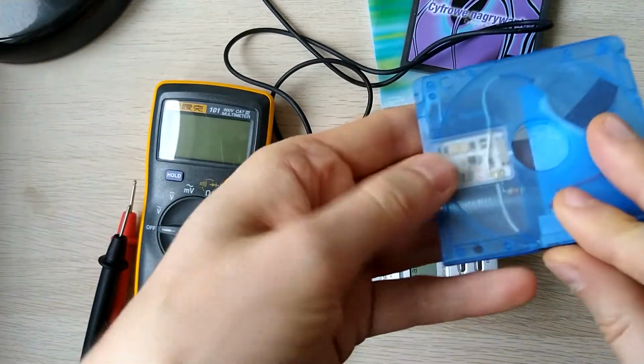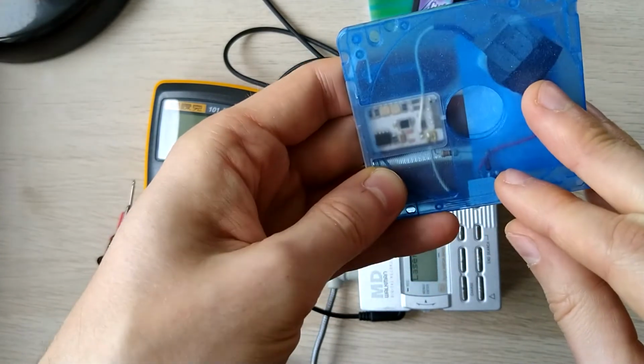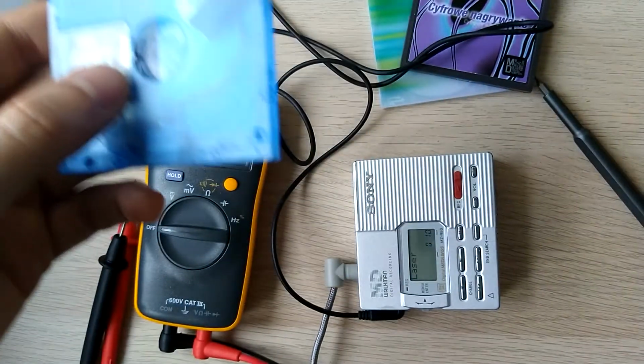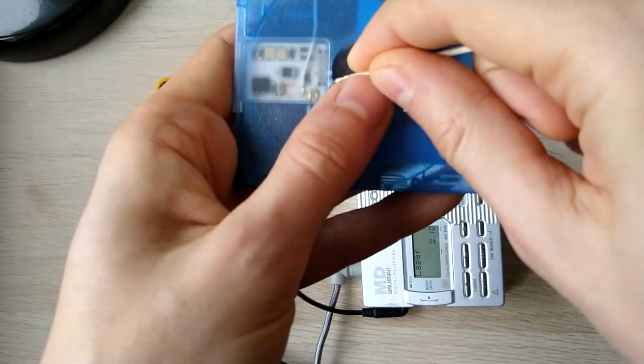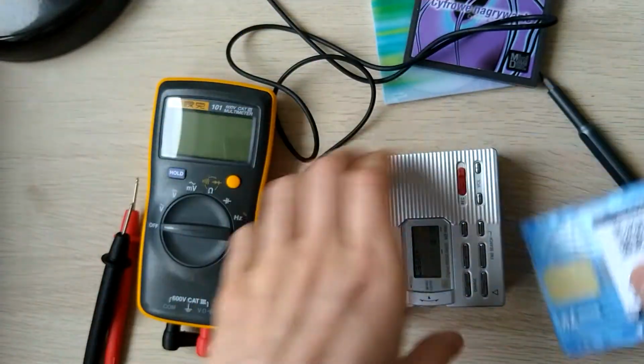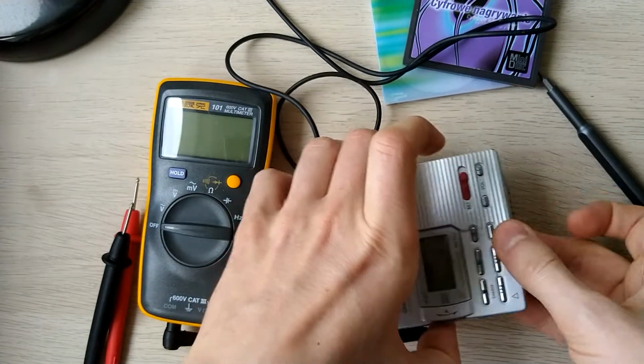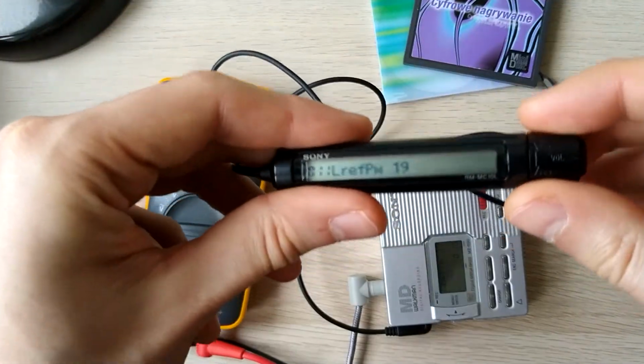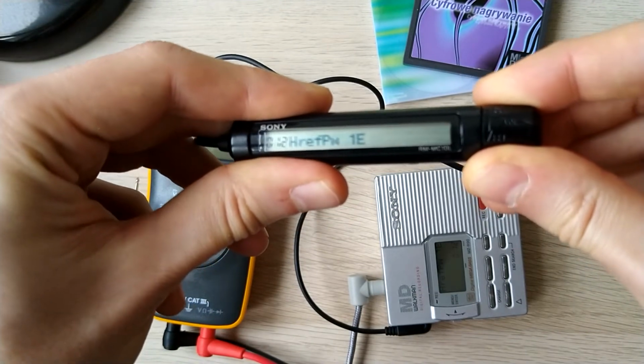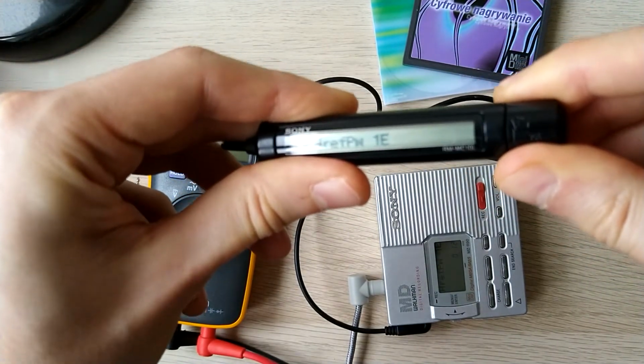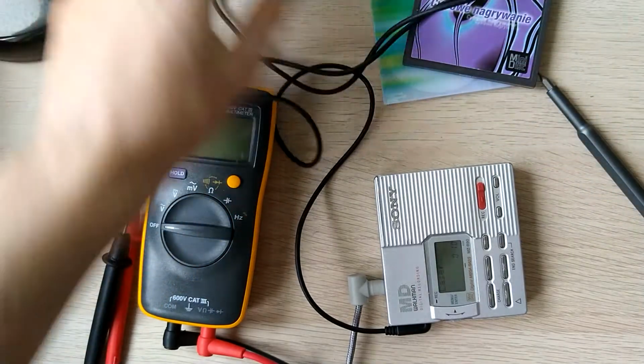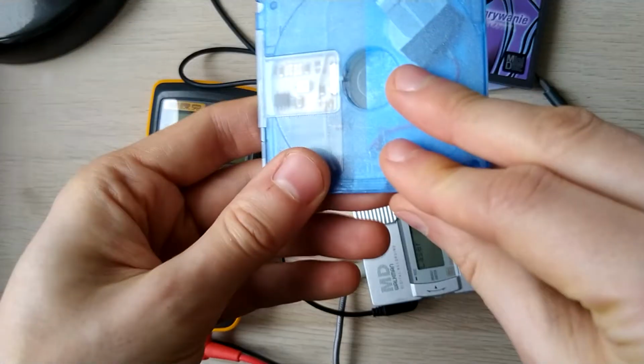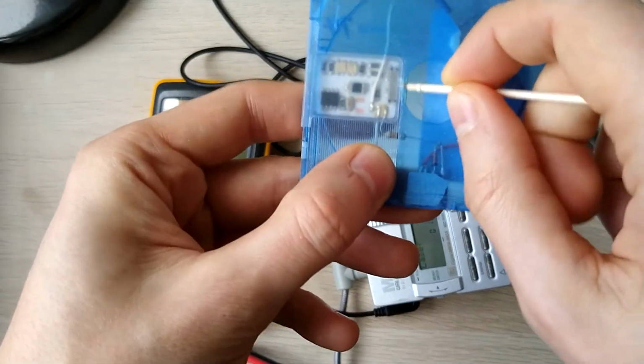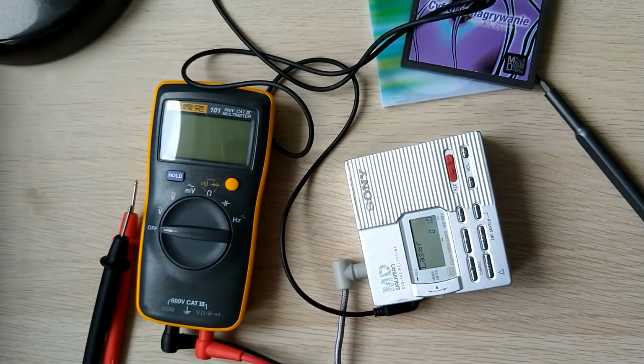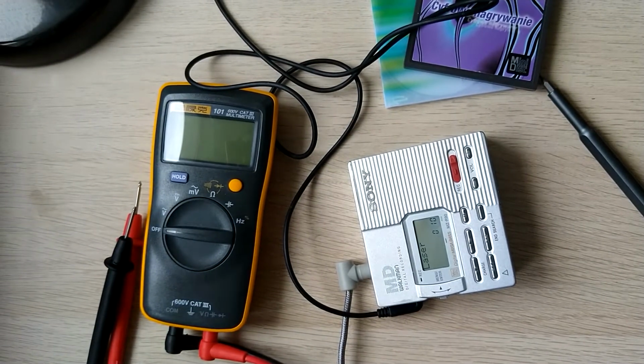Let's have a look at the meter. I have 2 green LEDs blinking, so the LREF value is in range. Let's check the HREF value. HREF value is also fine, so no adjustment here is necessary. Then we can move on to the actual auto adjustment.